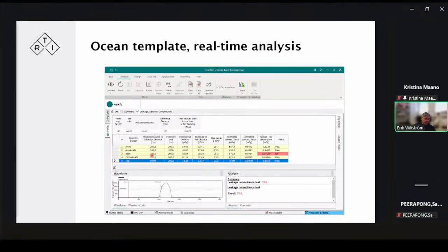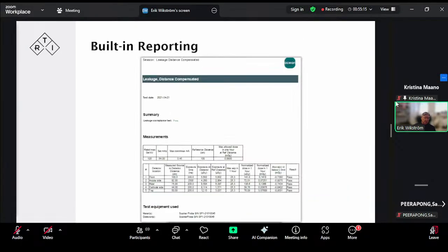So here you see that we're positioning at 2 meters, but we get a fail here. And why is that? Well, probably because the position was not at 2 meters, it was actually at 75 centimeters. So if we enter that value, after we use the tape measure, the calculations are redone and we get a pass and everything is fine. Once that is done, you can also produce a report with all the data for each position and serial number of the scatter probe for traceability.